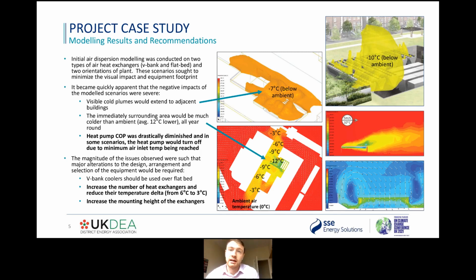Back to the drawing board, and we came up with some design alterations to do with essentially the selection of the coolers, the orientation of the plant, and a couple of other things, such as increasing the number of the heat exchangers, so reducing their temperature delta from 6 to 3 degrees. So instead of the air cooler exchanger reducing the air temperature by 6 degrees, it reduces it by 3 degrees, so that the net cooling of the air on an individual basis was reduced.